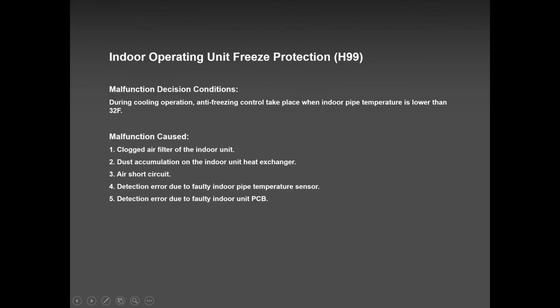H99. Once again, H99 will never ever trip in heat mode. H99 is designed for cool mode, dry mode, or auto mode error. It is not an error that is programmed in heat mode. So please keep that in mind: if you get this H99 in summertime, check if the coil is dirty, check if you are low on refrigerant, or check if the homeowner selected dry mode when there is not enough humidity to take care of the indoor coil.